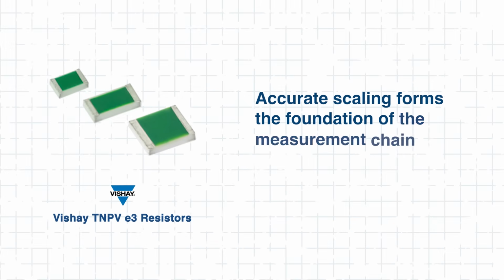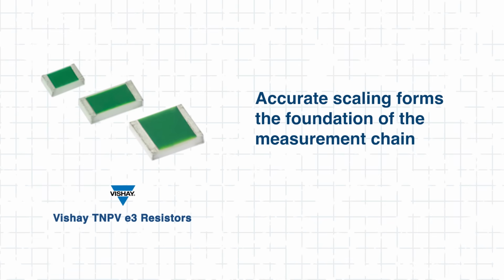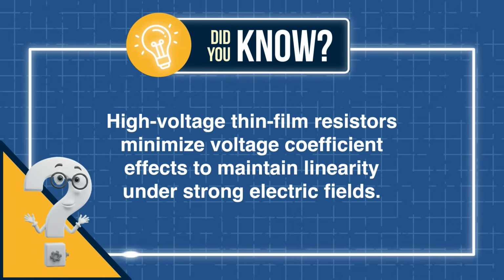Proper voltage division not only protects downstream components, but also establishes the accuracy foundation for the entire signal chain. High voltage thin film resistors are engineered to minimize voltage coefficient effects, which helps maintain measurement linearity at elevated electric field strengths. By safely reducing the voltage first, the design prepares the signal for isolation and amplification in the next stage.